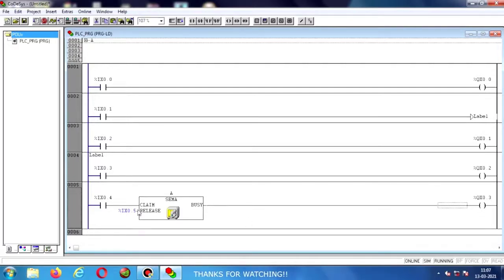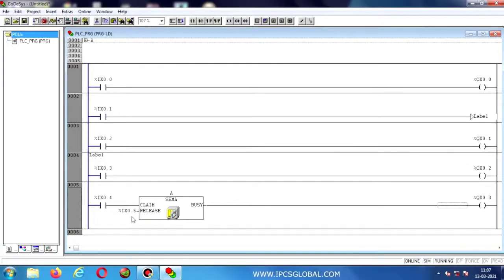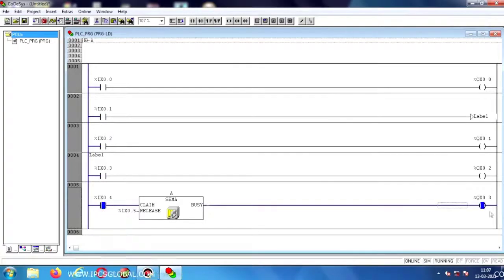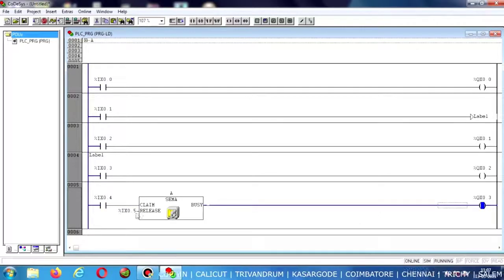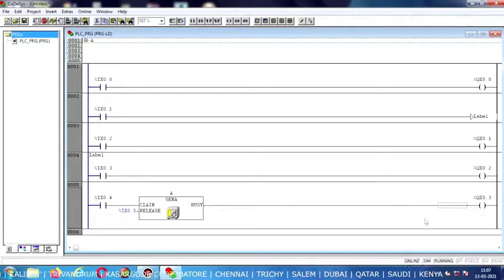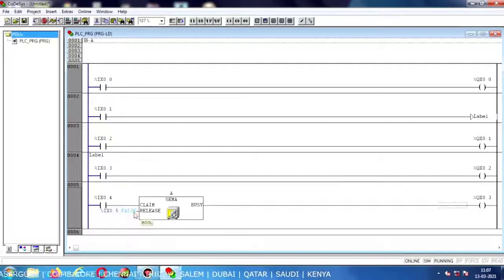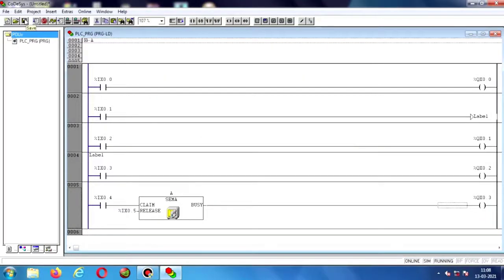Now I am going to release the function — enabling the Release function, and the output coil will be reset. Disabling the release, then enabling the input contact again — the output will be on. Even if we disable the input contact, the output stays set. Now enabling the Release — the output coil will be reset. This is the SEMA instruction in ABB Codesys software. Thank you.